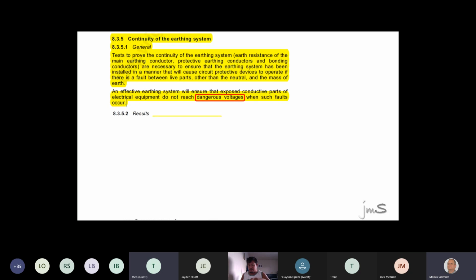So guys, if I say to you, do an earth continuity test, it is to ensure that anything which is metal is at the same earth potential. If not, a couple of things can happen. Here comes the general knowledge. We would have covered this in chapter 1 and testing, and then transformers. We touch on it with motors everywhere. You want to make sure that your touch voltage does not rise above 50 volts AC. If it does, it can shock you. Guys, if the resistance is not low enough in fault conditions, there's a possibility that your protection devices will not trip. You guys happy with that as well?